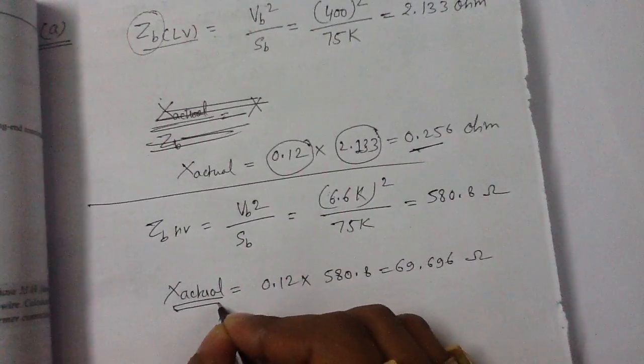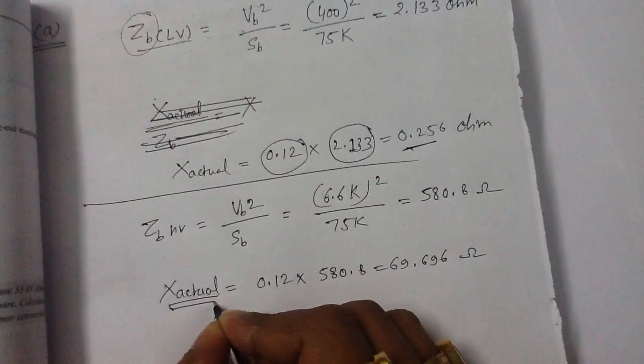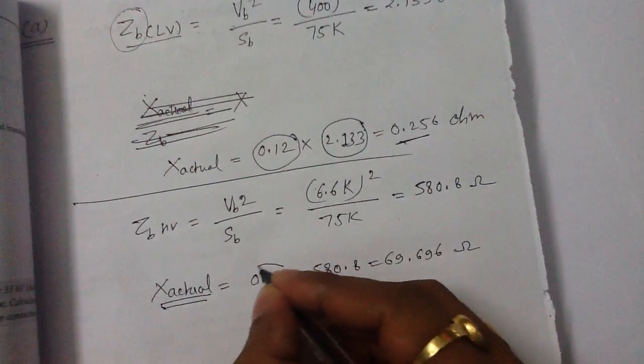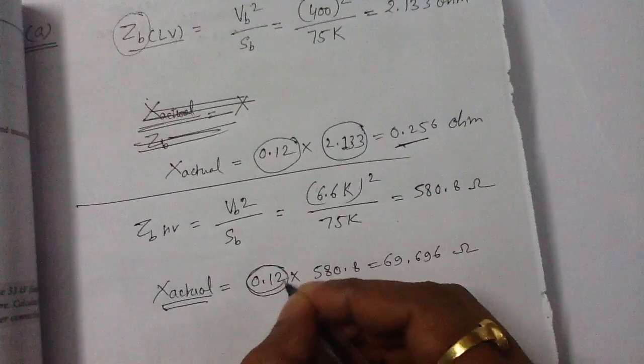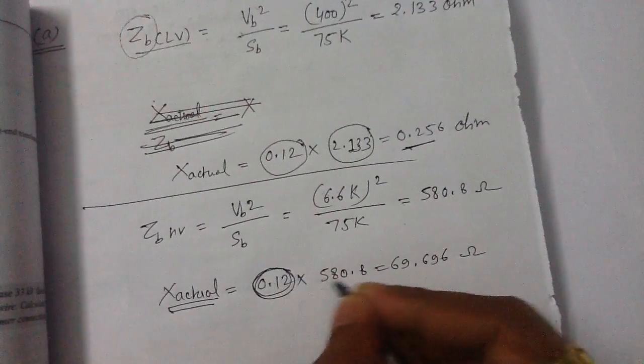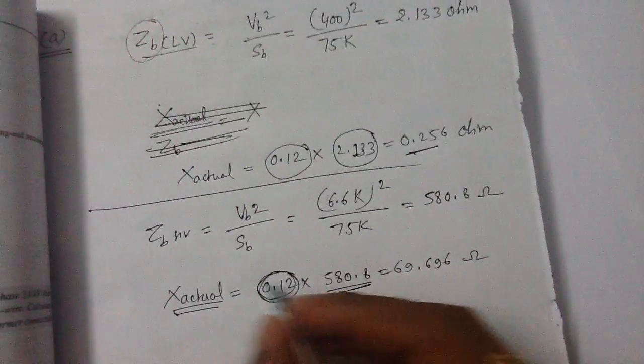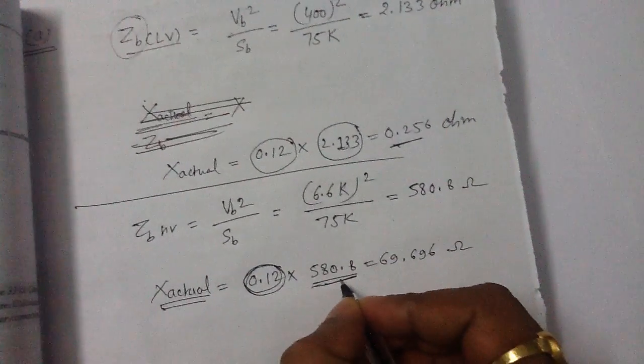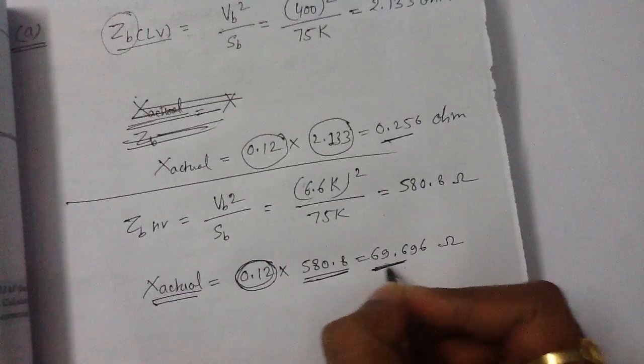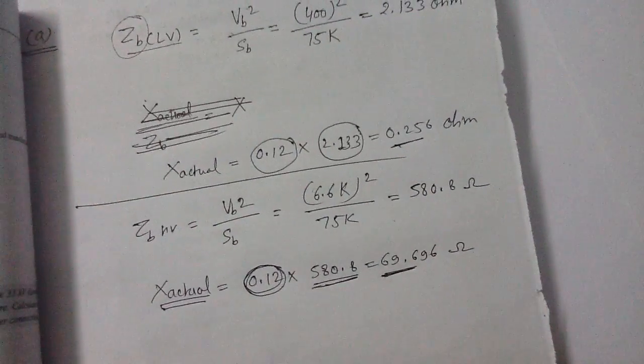Calculating 6.6 kilo squared divided by 75 kVA gives a base impedance of 580.8 ohms. To find the transformer reactance referred to the HV side, we multiply the per-unit reactance by the base impedance on the HV side, giving 69.696 ohms.